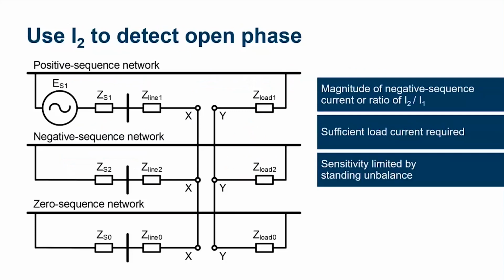So one thing that we can use to look for an open phase is our sequence components. We can look at our negative sequence current. For an open phase condition, we're going to see negative sequence and zero sequence current. What we can do is look for a high magnitude of negative sequence current on the power system. And even better, we can look at the ratio of negative to positive sequence current, so that's going to be a percentage of our total loading on the system. Now, one thing to keep in mind is that we need a sufficient amount of load on the conductor, on the phase where we have the conductor break, on that three-phase branch, in order to be able to detect this.